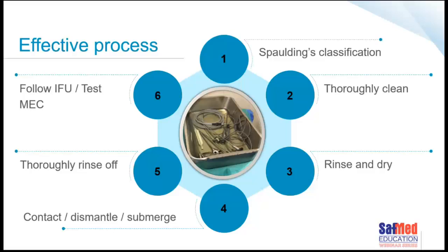Very important now is that the device that you're about to put into the high-level disinfectant is thoroughly cleaned with the correct type of detergent. And you know how to thoroughly clean a device. Once you've thoroughly cleaned the device, you need to rinse it thoroughly before you put it into the high-level disinfectant, as well as dry it, remove the residual moisture. If you take the device and it's quite wet and you put it into the high-level disinfectant, by the end of the day, when you do that repeatedly, the high-level disinfectant will be so diluted, it will no longer be effective.